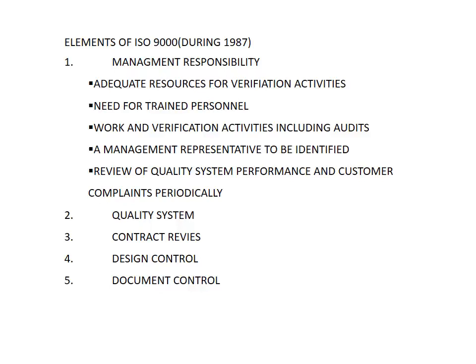Documented input requirements are reviewed and any discrepancy or ambiguity in the requirement is to be resolved. So if there is any confusion, it is the responsibility of the design departments. They should resolve such ambiguity. Verification of the design at all levels of development is carried out and documented. All design changes are approved, documented and verified. So with the passage of time, when certain parameters change or we redesign the product, it should be approved, documented and verified with the appropriate authority.